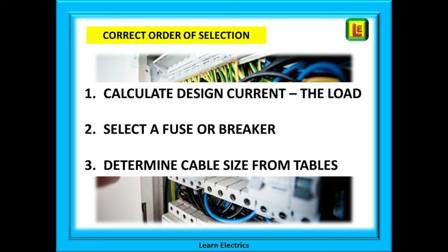And now we can determine the size of cable to install by looking at a set of standard tables. We use the symbol IZ for cable rating. If we know how much current is to flow through the cable, the tables will tell us the cable size to select. Too small a cable and the cable may be damaged or even catch fire. Too big a cable and the customer or you are paying for extra copper that you do not need.